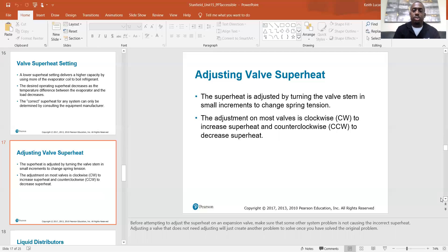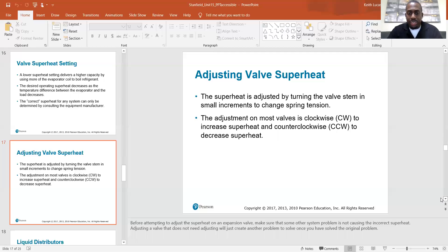Superheat is adjusted by turning the valve stem in small increments to change the spring tension. Turning clockwise increases the superheat; counterclockwise decreases it — righty-tighty, lefty-loosey. Before attempting to adjust superheat on an expansion valve, make sure some other system problem is not causing the incorrect superheat. Adjusting a valve that doesn't actually need to be adjusted will just create another problem to solve after you solve the original problem.